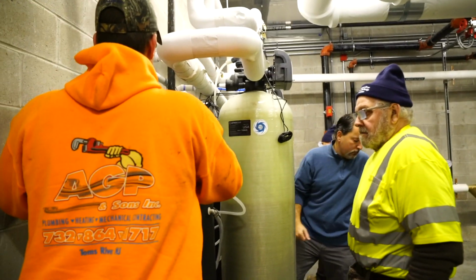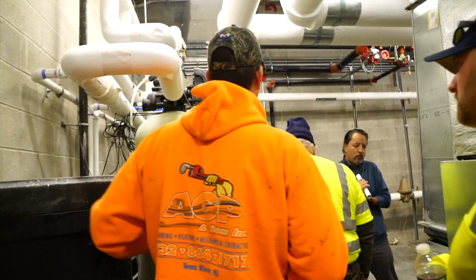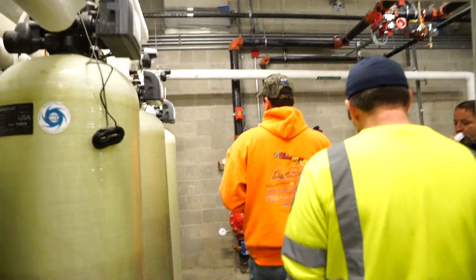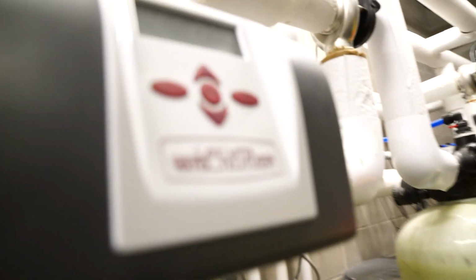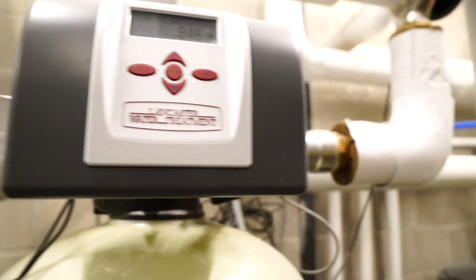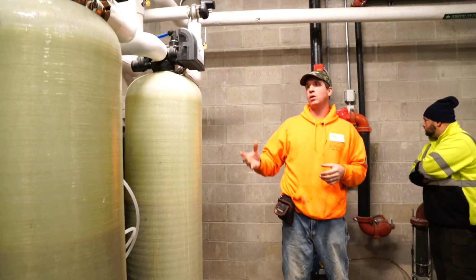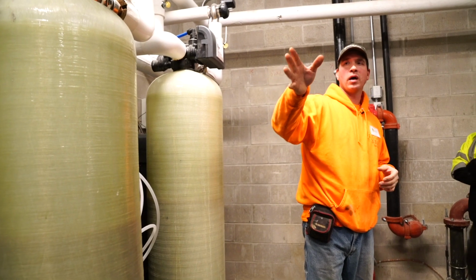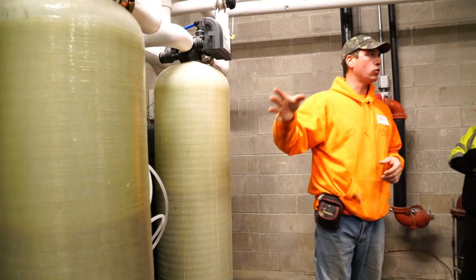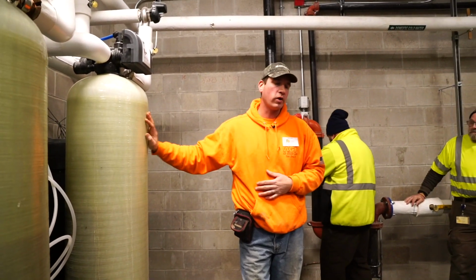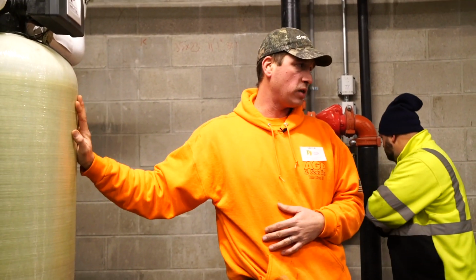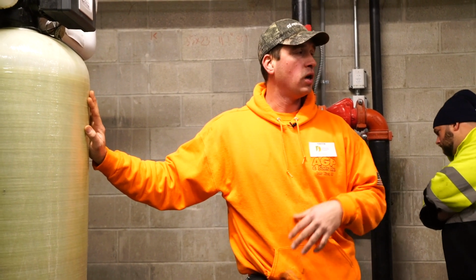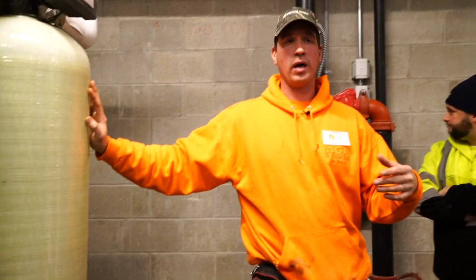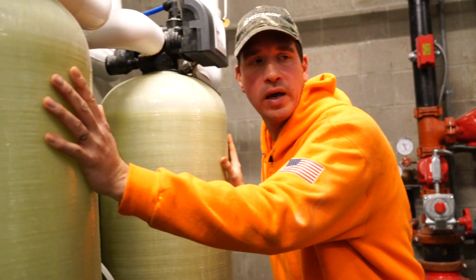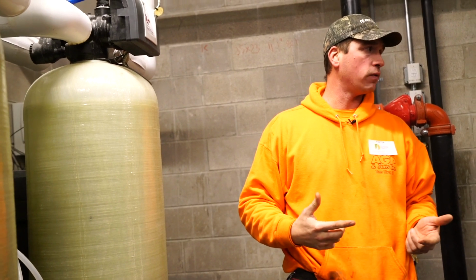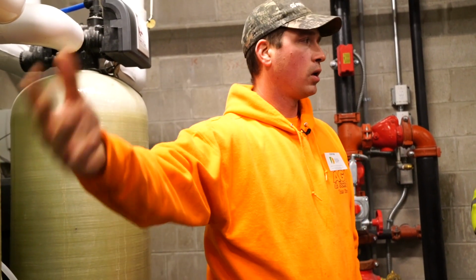The way this system works, all 3 tanks are never running. It's on demand. So basically, if the building's calling for, there's multiple fixtures going, it goes at a 25 gallon per minute flow rate. So the tanks will automatically, over time, just cycle through each one, so they're always getting an even amount of use. But if the building's calling for 24 gallons per minute right now of water being used, 1 tank will be in use. If it goes over 25 gallons per minute, now we're up to 28, 2 tanks are being used just to handle the gallons per minute of the flow rate. And same thing, now we go over 50, it goes to the next tank.